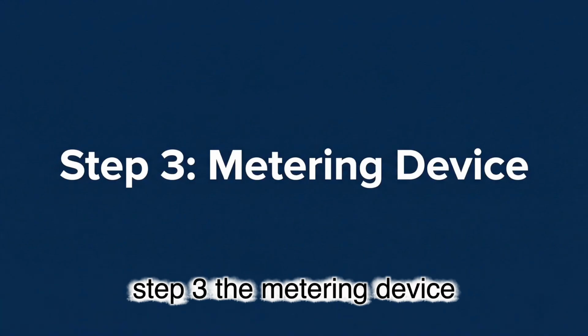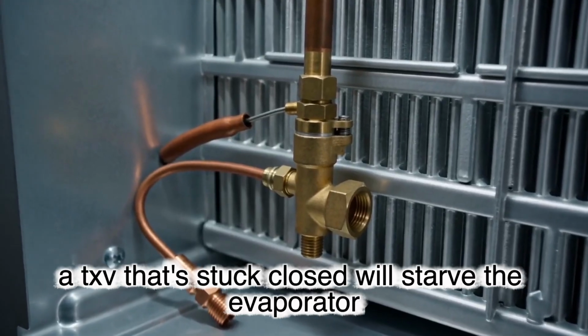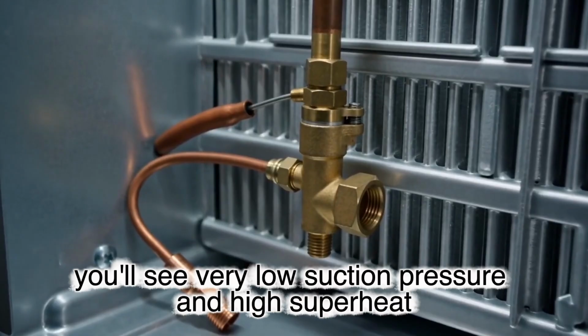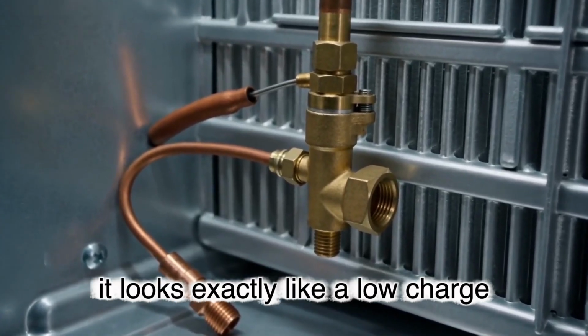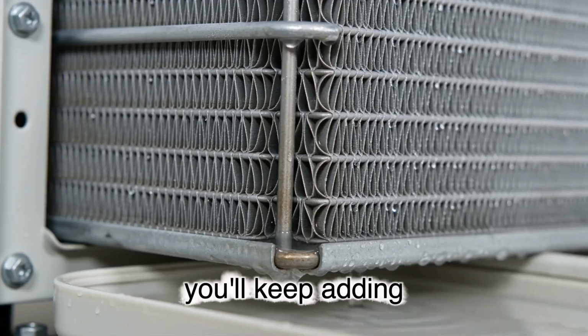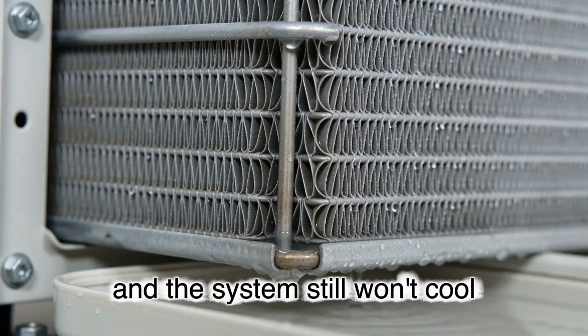Step 3, the metering device. A TXV that's stuck closed will starve the evaporator. You'll see very low suction pressure and high superheat. It looks exactly like a low charge, but adding refrigerant won't fix it. You'll keep adding until you've overcharged the high side, and the system still won't cool.